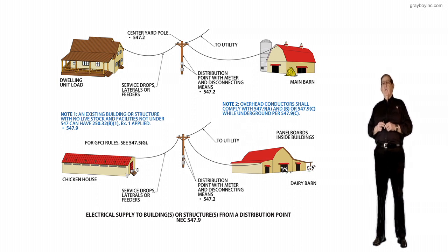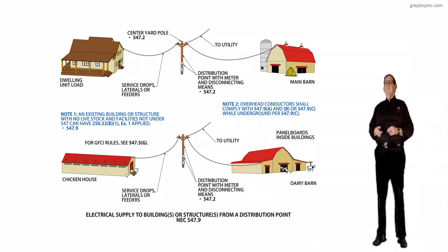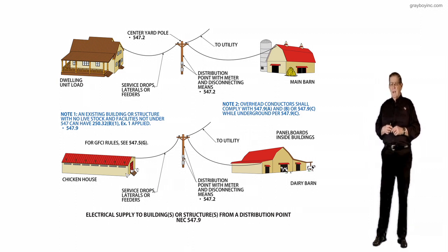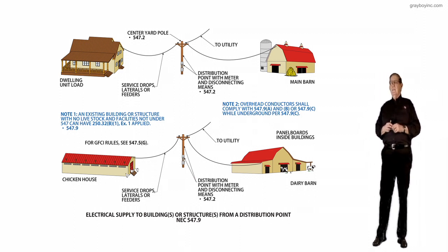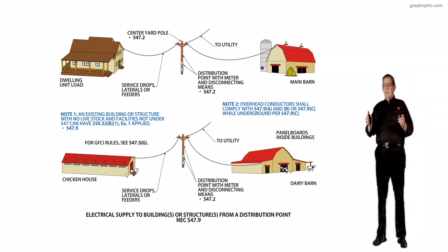So if you are wiring these areas, you want to make sure: is it just grain handling, a residence, when was it installed, or is it chicken coop areas and housing of chickens for laying eggs and so forth? Is it a dairy barn where they're having electric milkers that in some cases would milk the dairy cows and so forth? Know the system that you have to provide and where it could be a 3 or 4-wire system, and that's what this revision is trying to point out to the designer or the installer as well as the inspector.